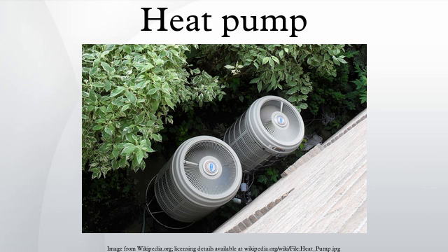Efficiency. When comparing the performance of heat pumps, it is best to avoid the word efficiency, which has a very specific thermodynamic definition. The term coefficient of performance is used to describe the ratio of useful heat movement per work input. Most vapor compression heat pumps use electrically powered motors for their work input. However, in many vehicle applications, mechanical energy from an internal combustion engine provides the needed work. According to the US EPA, geothermal heat pumps can reduce energy consumption up to 44% compared with air source heat pumps and up to 72% compared with electric resistance heating.